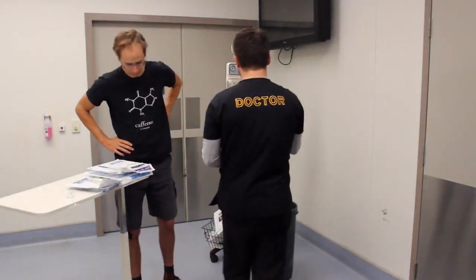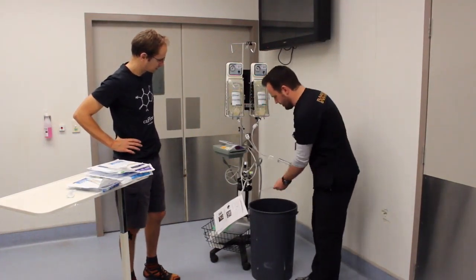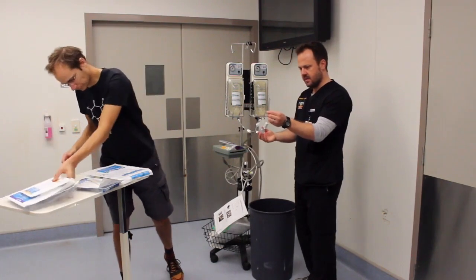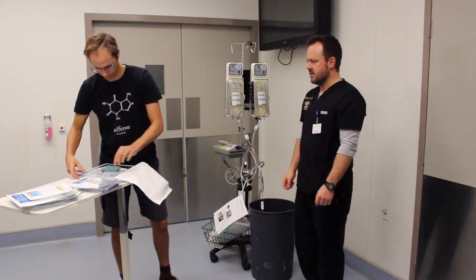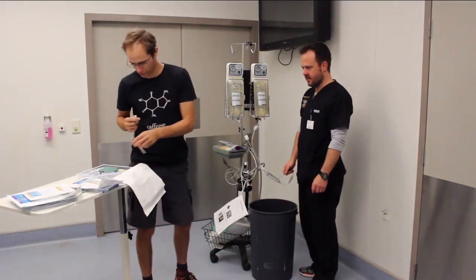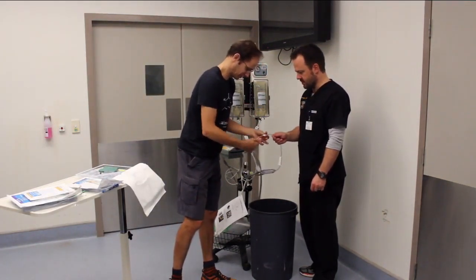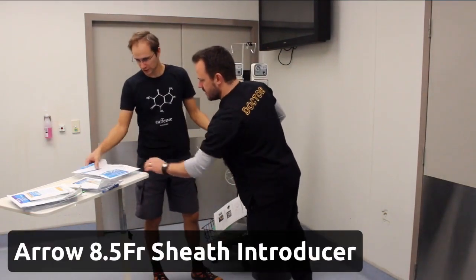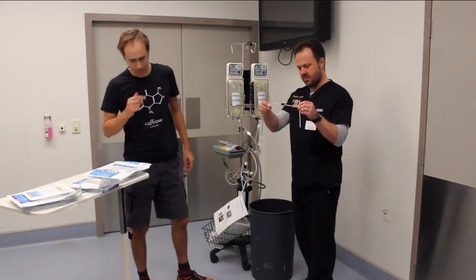So, here we go — the large-bore IV access device showdown. We've got the Ranger rapid infuser here, which is the pressure system. We've connected it to a single exit flow channel, taking the blood warmer off. We're going to run some fluid through and see how fast it goes. I'll just attach that to the Luer-lock, just for consistency.